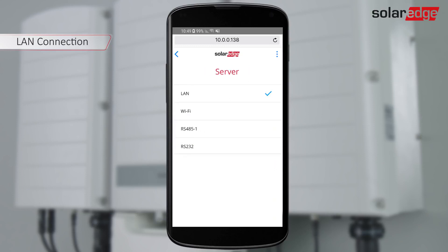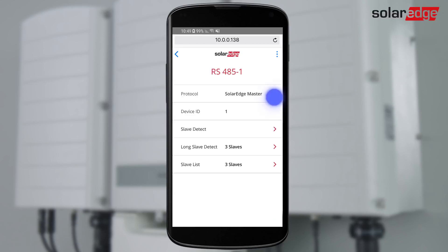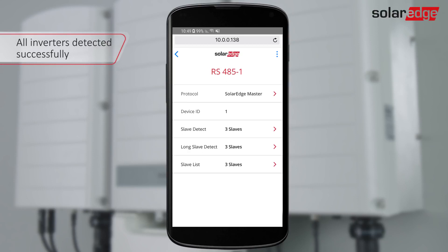The default configuration is LAN. If you are not using Ethernet for connection to the monitoring platform, select the relevant wireless option. If multiple inverters are connected on an RS-485 bus, in the master inverter, enter the communication settings menu and select RS 485-1. Then select Protocol, SolarEdge Master and select Slave Detect. The master inverter detects the other inverters on the screen.